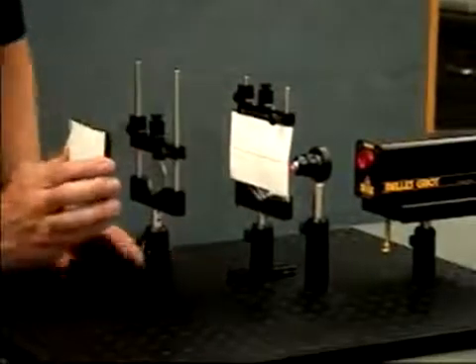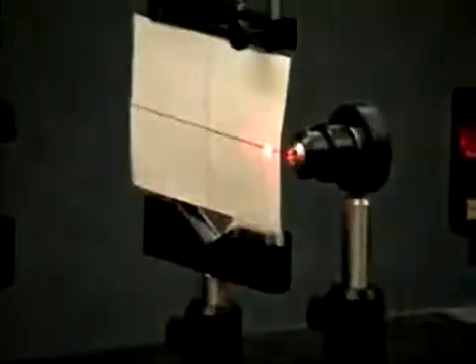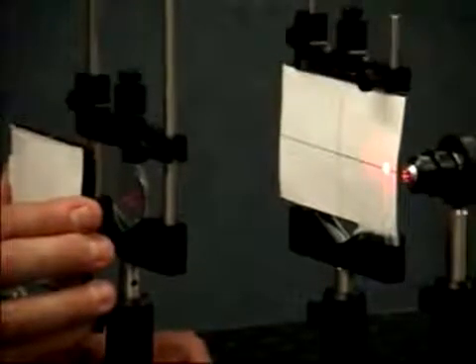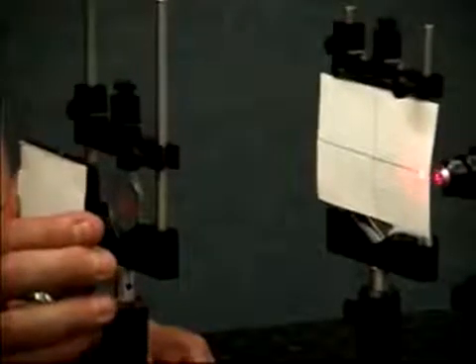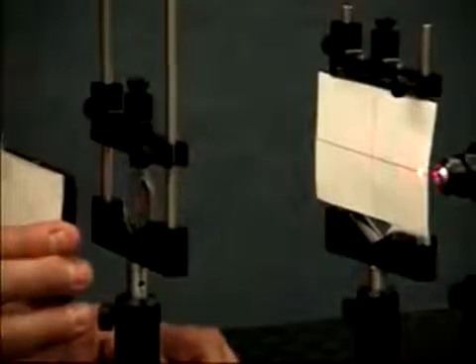Now, what we're going to do is take our plane mirror and we're going to use it to reflect the light coming through the lens back just off axis. And if you can zoom in to this here, you can see the spot there. We're going to zoom it right off axis there and we're going to look at the size of this spot as we adjust the position of the collimating lens. What I'm going to do is adjust the position of the collimating lens and find the point at which that focus spot is basically as sharp as possible and we look like we have it about there. If I go a little bit farther, it starts to expand again. If I come back this way, it starts to expand again. So what I want to do is find the spot at which the reflected light just comes to a point off axis.